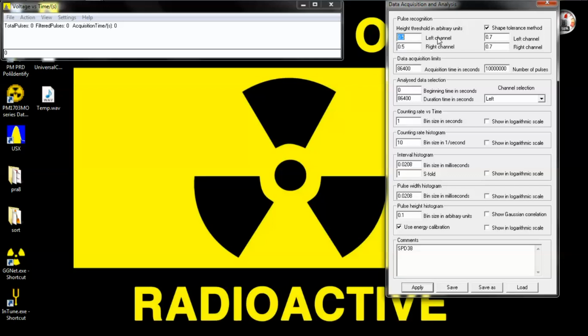And pretty much I have this set the way I'm going to use it right now, 0.5 to 0.7 right here. You're going to want to play with this until you get it right. The actual manual explains more detail about this. But basically when the numbers are set really low, like 0, they have to be exactly the pulse shape to be counted. So if hundreds of pulses go in, I'm only going to probably detect 1 or 2 of them that are perfectly right. So very few detections will be right.